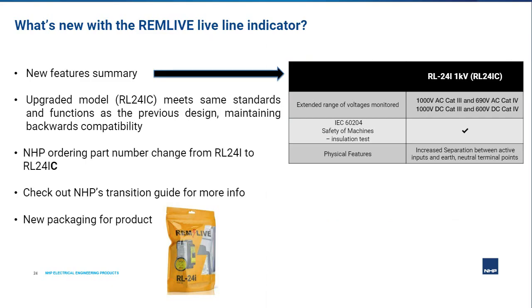So what's new with the REMLIVE live line indicator? It was advised earlier that the REMLIVE product has undergone upgrades to the original model. So let's summarize some of these points as per the table shown, most of which we have already covered in detail. Number one, the extended voltage range that it monitors, which is now 24 to 1000 volts AC and 26 to 1000 volts DC. Lines to IEC 60204 for safety of machines for insulation test. Increased separation between connection points for wiring convenience.